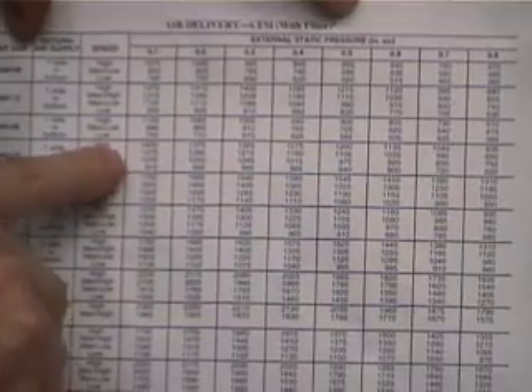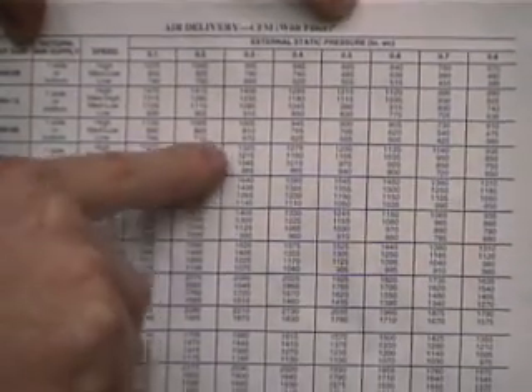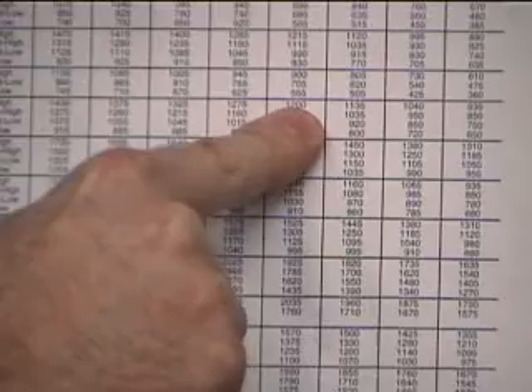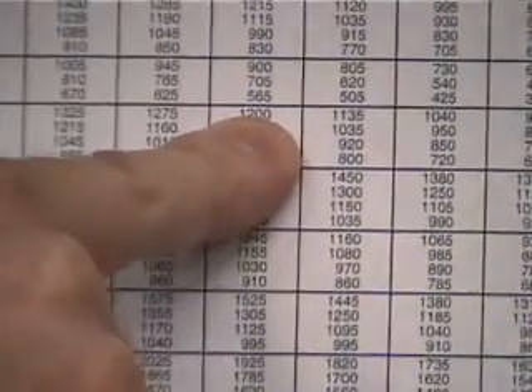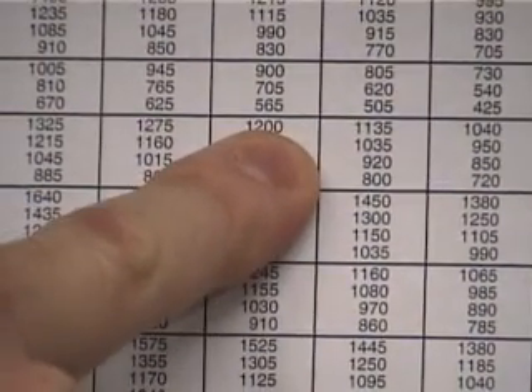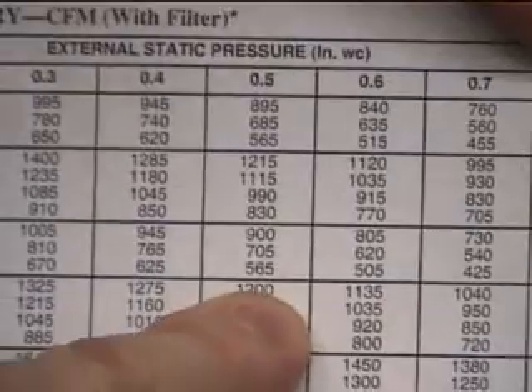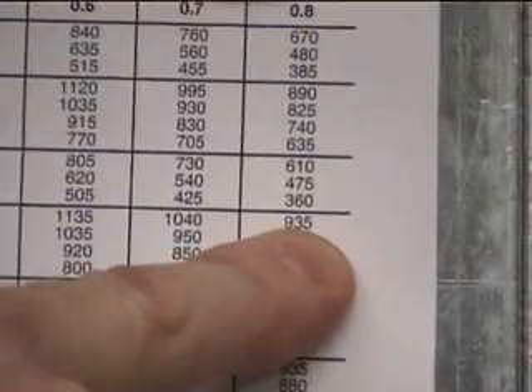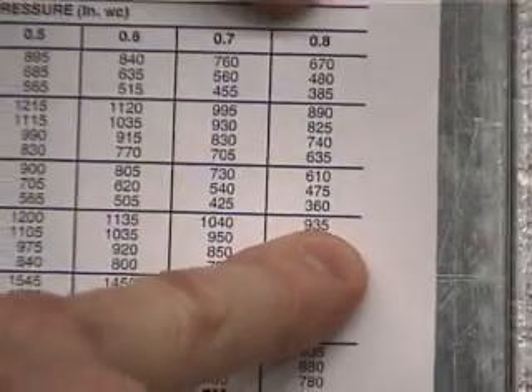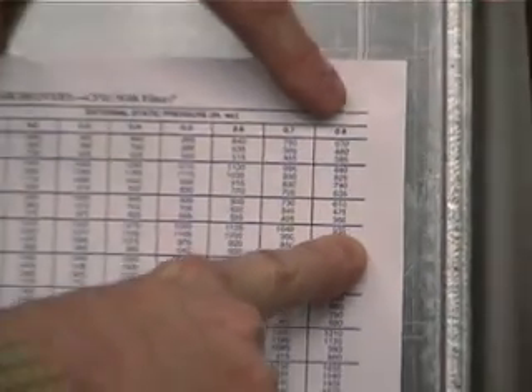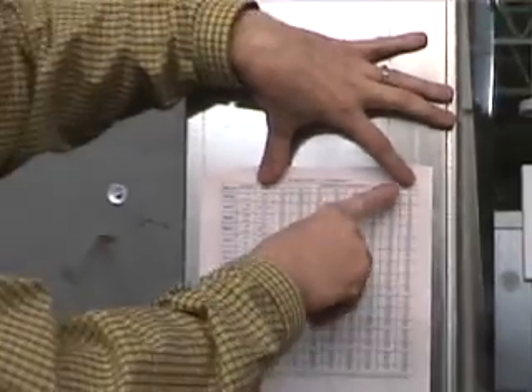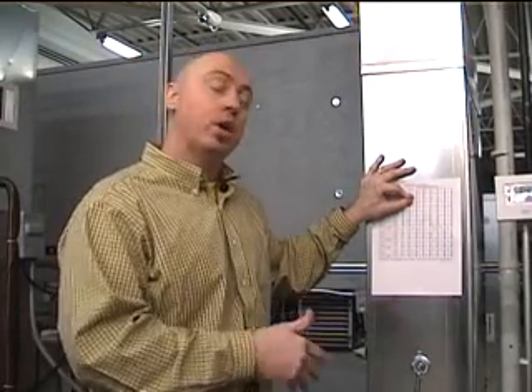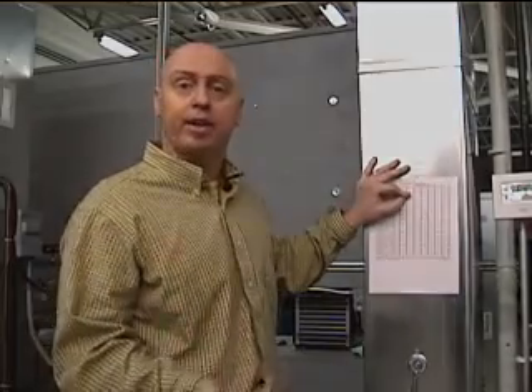So what I do is say I'm on high speed, I have this unit, I come straight across to 0.5, is 1,200 CFM. Now, if my static pressure was actually moving up this way, and my static pressure was 0.8, I come all the way across here. Now I've got a unit that is operating with 935 CFM instead of 1,200. And a lot of times, you'll see static pressure about 1 inch. That's clear off this chart. And when it becomes off the chart at 0.9, 1 inch, you might be moving 800 CFM on a 3-ton drive. So how well does an air conditioning unit operate off of 800 CFM when it's a 3-ton air conditioner?